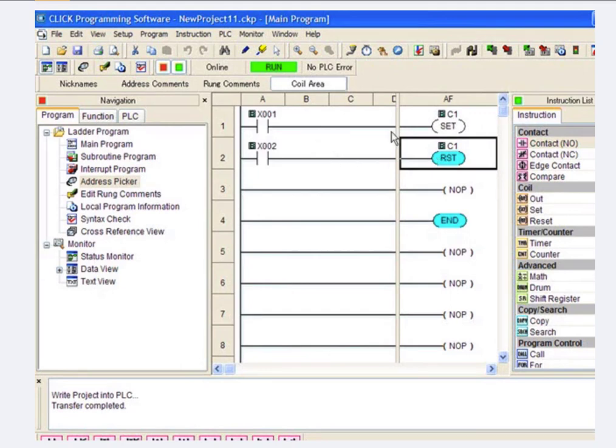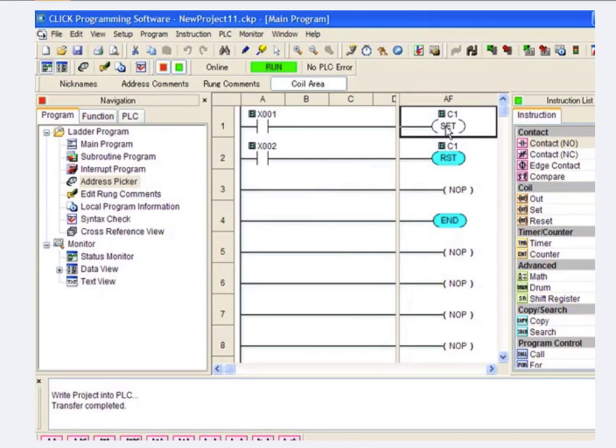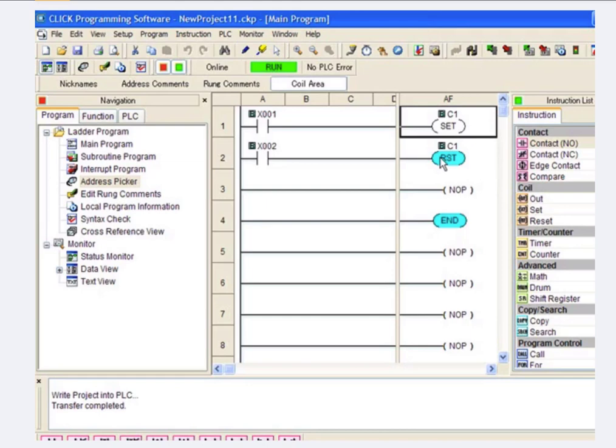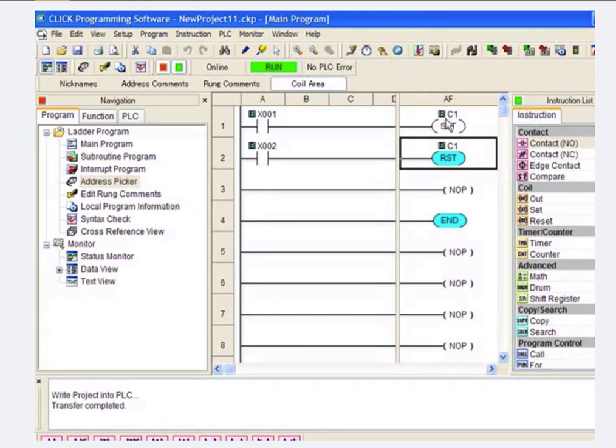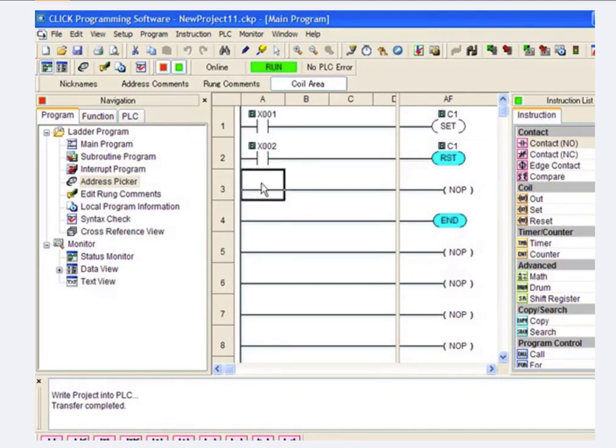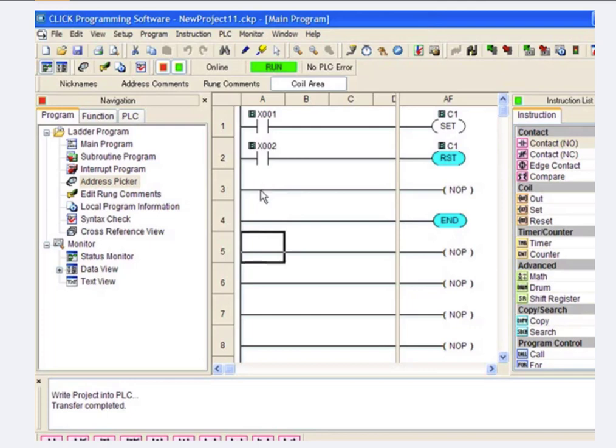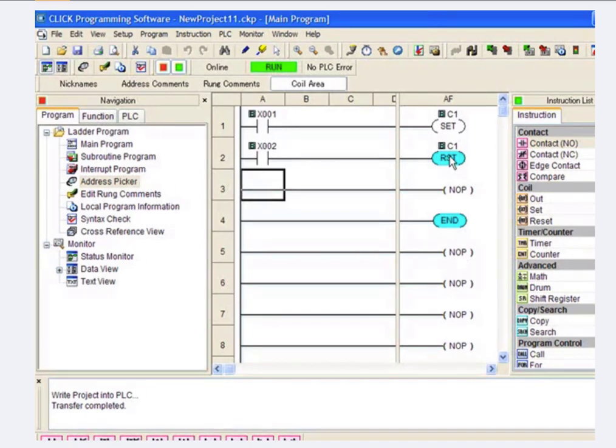So basically, what I did is I took a ladder rung that was controlling a Y, which is a physical, real-world output to some device, such as a solenoid or motor. I replaced it with a C, which is an internal bit, not a physical address that goes out to the real world and turns something on. But I can then use this C later on in code to perform some other action for me. So that's the beginning of where we start using the Cs internally in the PLC to do other functions for us in ladder.